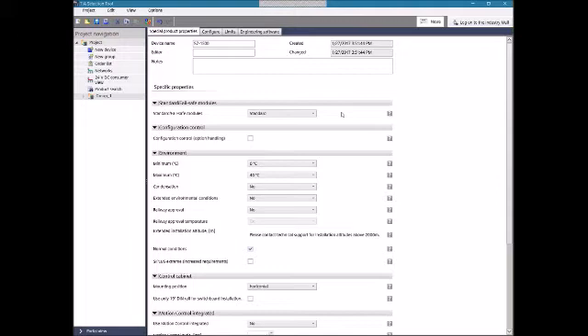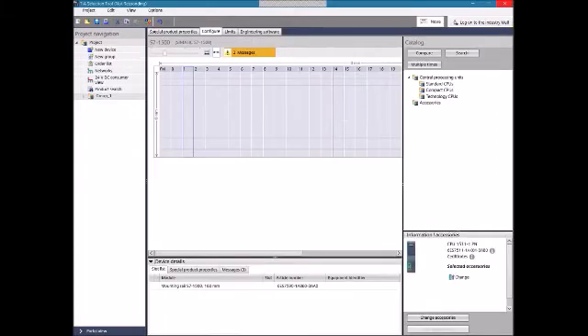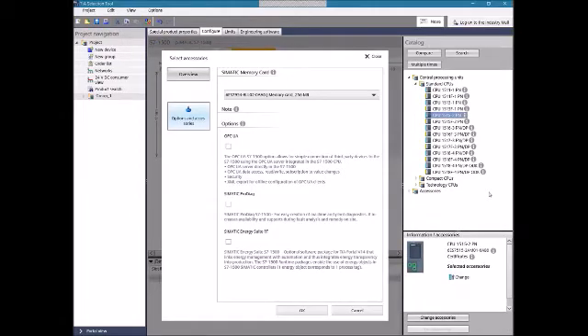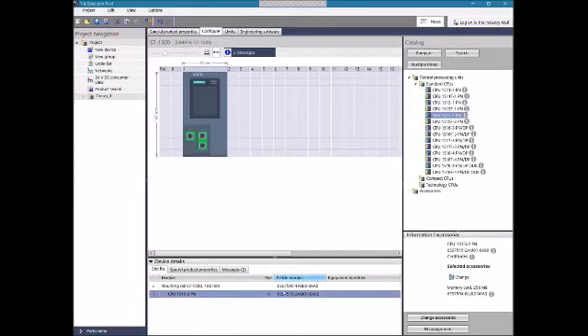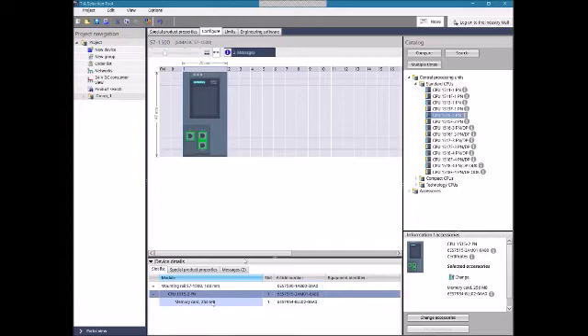It's going to give us everything we need to actually order a project and get going without worrying about missing parts. We can see the 1500 listed here with all the CPUs we can pick. When I double-click on one, any object that has options will show them to me. It's automatically picked a memory card, so I don't have to worry about that — it picks the size according to the processor. There are other options like OPC UA, but I'll keep the defaults. At the bottom of the screen, it's generating a bill of materials as we go. It knows we need a DIN rail, so it added it, and we can see the memory card was selected.